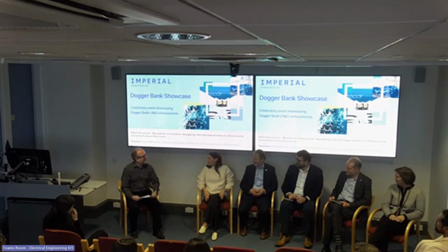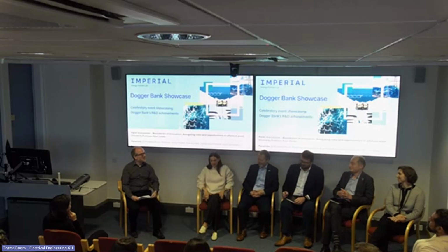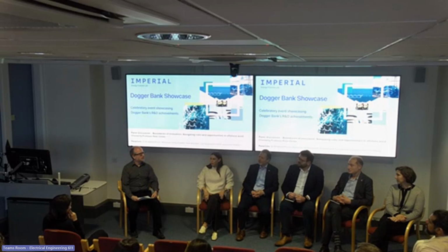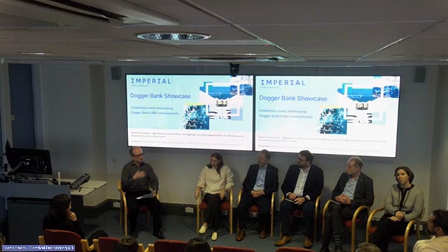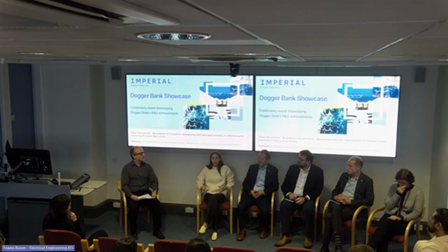I can give it a go, at least at the start, and then you guys can chip in. In terms of HVDC in general, and perhaps focusing on the technology that we have in Dogger Bank, which is a voltage source converter, but we've not gone the step ahead of that grid-forming capability onshore. So I think it's worth making that distinction. If we're talking about the benefits that HVDC can bring in terms of network stability and reliability, there are perhaps two items to highlight. One of them is improved dynamic performance, because we're talking about power electronics and a very fast control system. The HVDC system can react very quickly to disturbances or faults in the network.